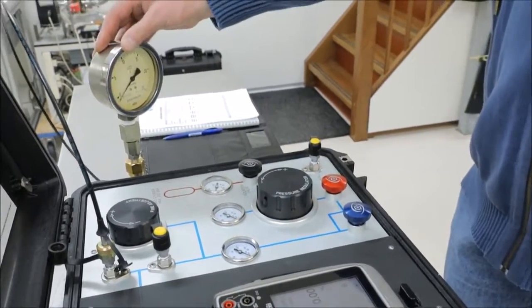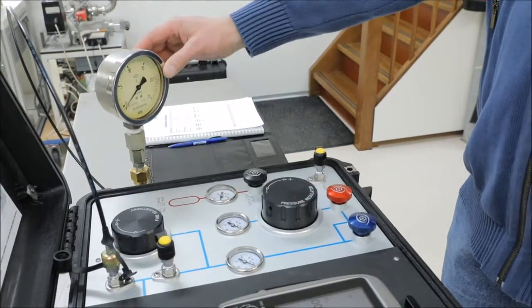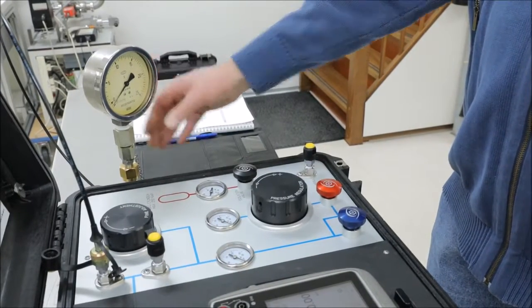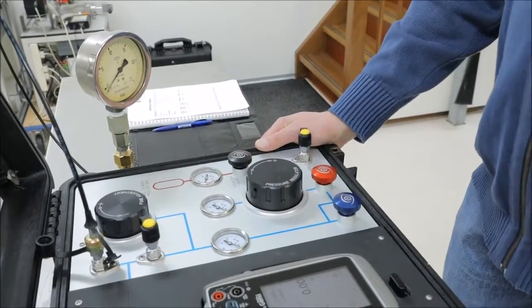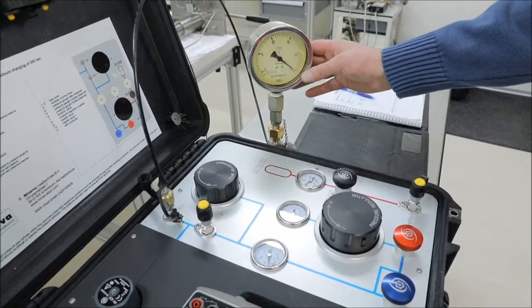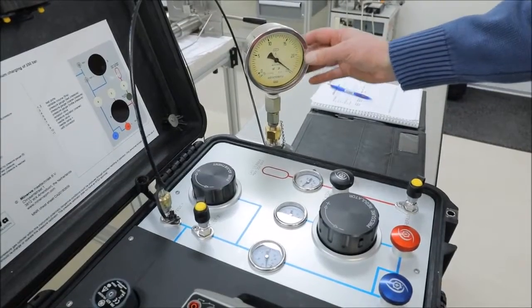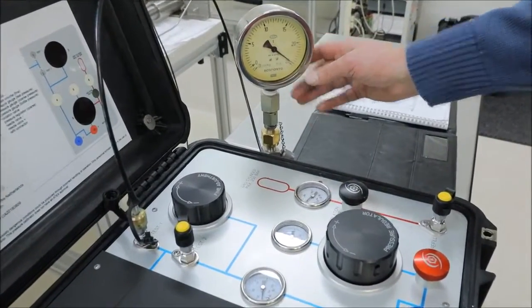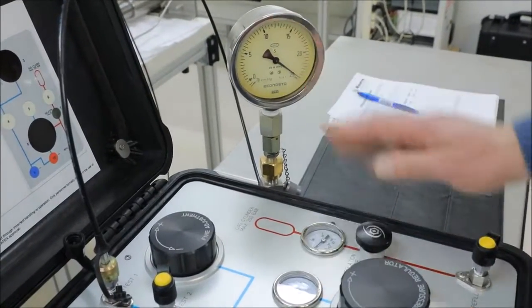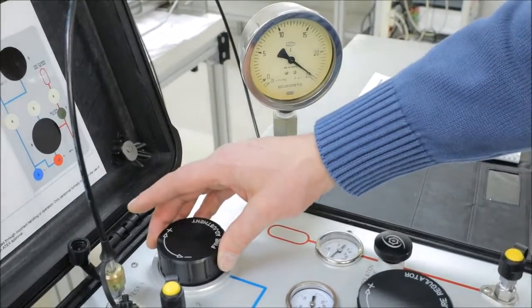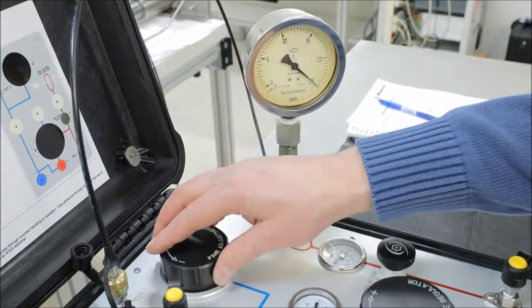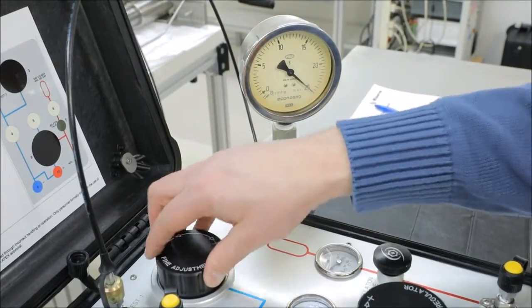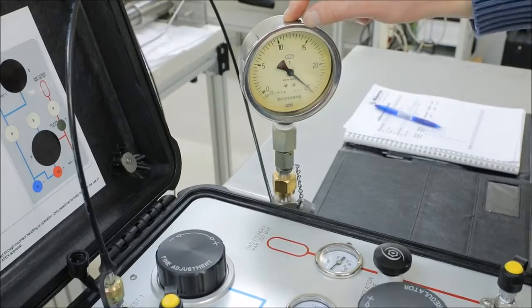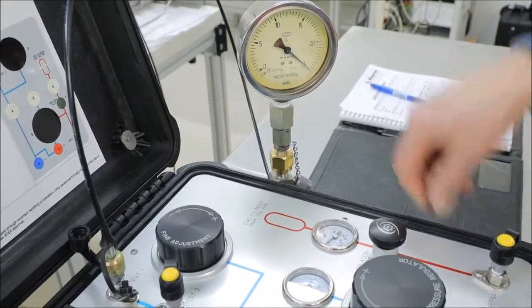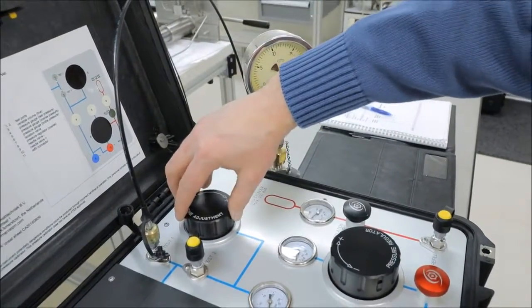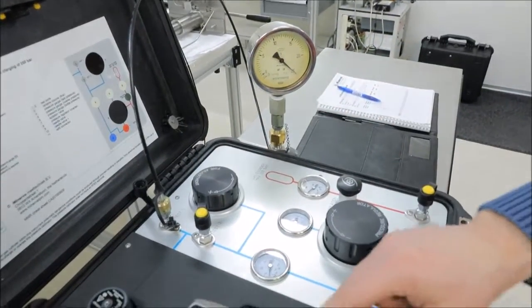Typically, if you look at the analog gauge, 5 bars, 10 bars, 15 bars, 20 bars and 25 bars are the points I want to calibrate, because those are the major intervals. So we performed the 15 and the 20 bar points, and now we are almost at the maximum pressure, the 25 bars. You see that the pressure still is slightly below 25 bars, and I want to manipulate the pressure until it's exactly at 25 by using the fine adjuster. At 25 bars, it's still very easy to manipulate the pressure, because it's a pressure compensated variable volume, and it will always rotate pretty smoothly even at 250 bars. So 25 bars, slightly adjusted, that's nominal, equals 24.86.